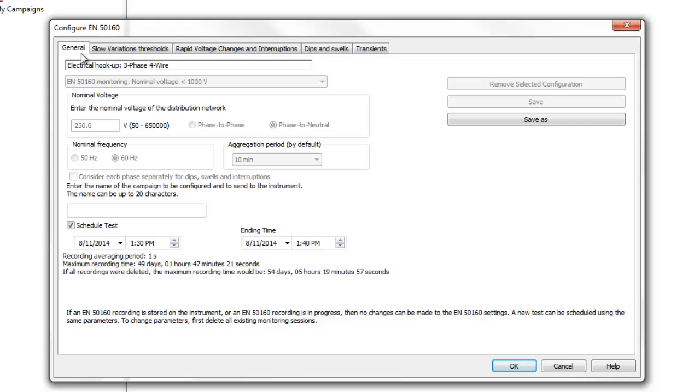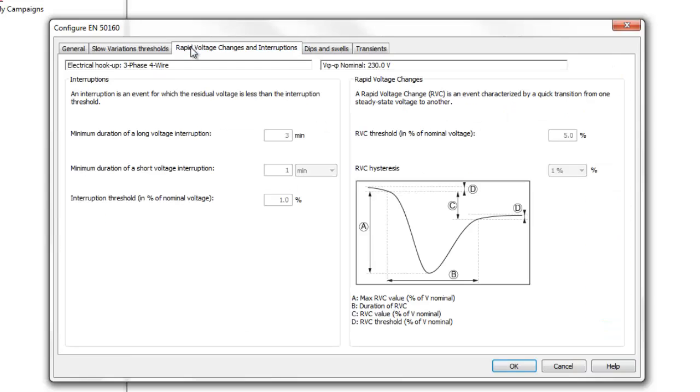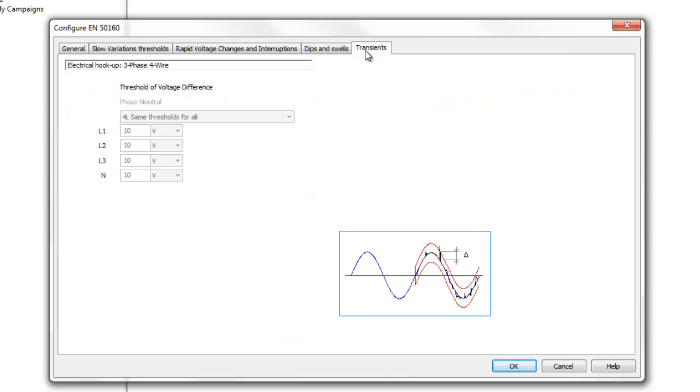You can also name and schedule an EN 50160 monitoring session. Slow Variations sets parameters for identifying how much a measurement varies from its acceptable value defined by EN 50160. Rapid Voltage Changes and Interruptions configures the monitoring session for detecting rapid voltage changes and interruptions in the system under measurement. Dips and Swells define settings for monitoring dips and swells, also known as overvoltage events. Transients sets conditions for capturing transients in the system.